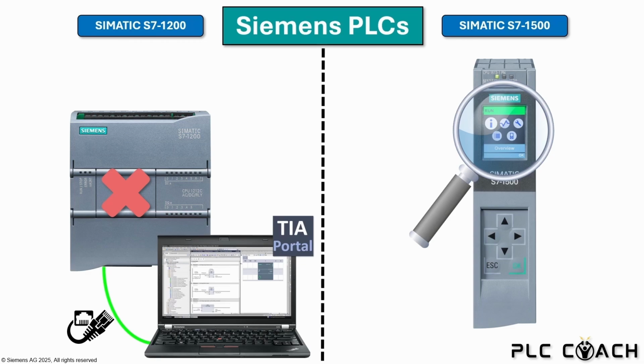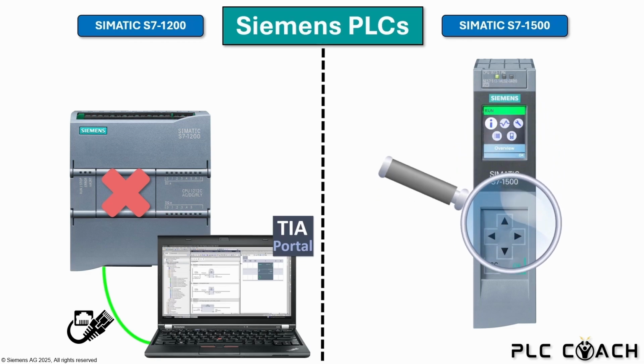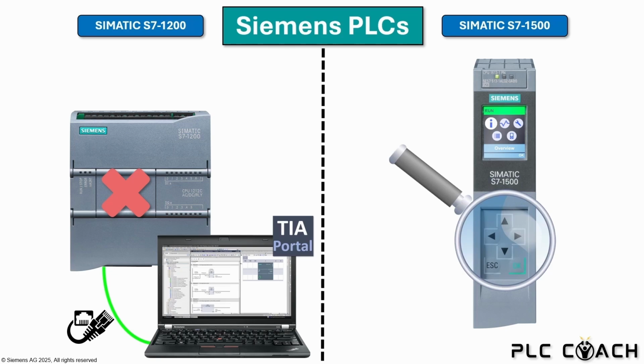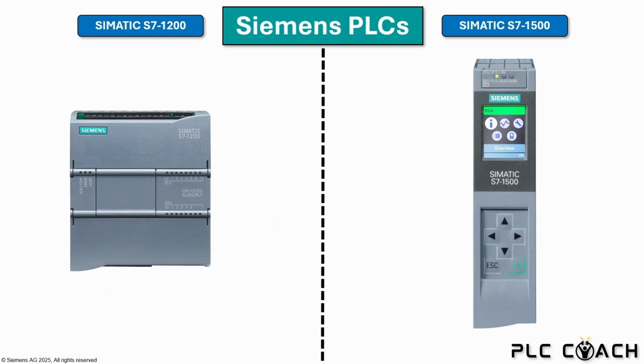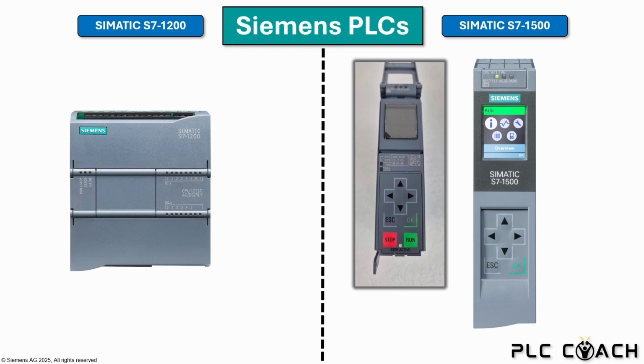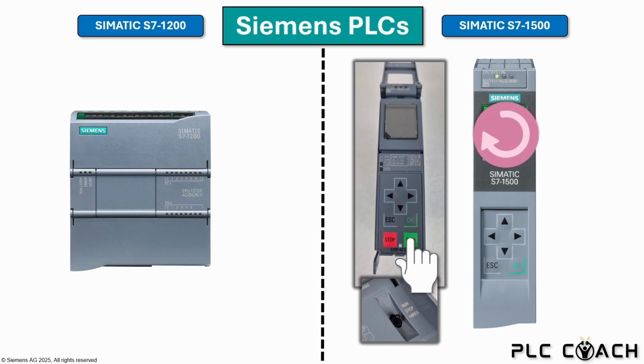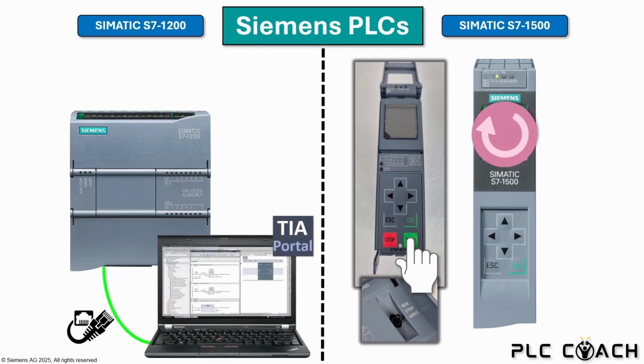The display on the S7-1500 is operated by using these buttons. The S7-1200, of course, does not have any buttons. When you open the front cover of the S7-1500, you will see two additional buttons labeled Start and Stop. These allow us to change the operating mode of the controller. If the CPU is in stop mode, the transferred program will not be executed. The program is only executed in run mode. On some controllers of the S7-1500 series, there is a small switch to change the operating mode. If you want to change the operating mode of the S7-1200, you will need a computer again.